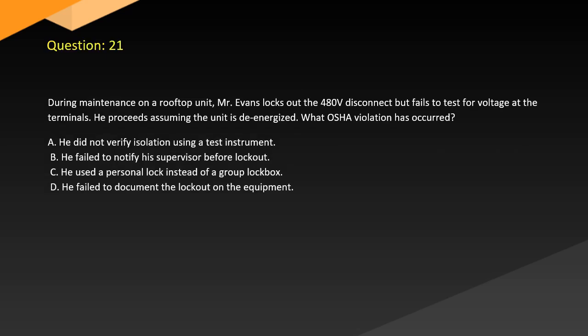Question 21. During maintenance on a rooftop unit, Mr. Evans locks out the 480 volt disconnect but fails to test for voltage at the terminals. He proceeds assuming the unit is de-energized. What OSHA violation has occurred? A. He did not verify isolation using a test instrument. B. He failed to notify his supervisor before lockout. C. He used a personal lock instead of a group lockbox. D. He failed to document the lockout on the equipment.